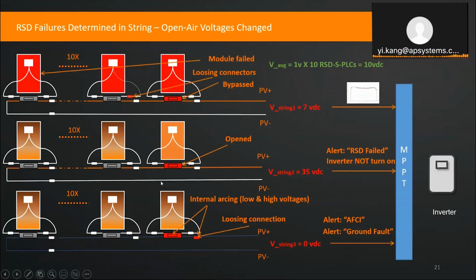Yep. Also, if for some reason the device is open here, meaning the device is shorted. For instance, you accidentally touched positive and negative before, and then the installer doesn't know and just hooks it up into your system, but the device is already shorted. Shorted means they lost the rapid shutdown function. And what's going to happen is we release this power directly. And when you measure the positive and negative on the open-air DC side, you will see a higher voltage, much higher than the safety voltage it's supposed to be. If you have that kind of situation, you should immediately know that, okay, some device is shorted.